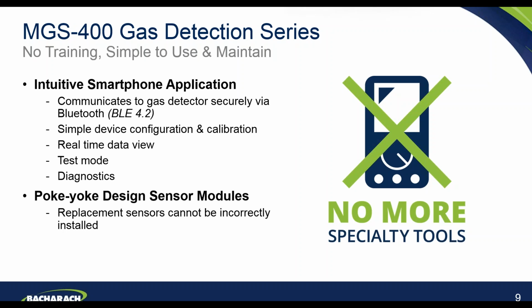In terms of the sensor modules themselves, they've been designed as a poka-yoke design, which essentially means that there is no way those sensor modules can actually be incorrectly installed. You can't put them in upside down or put them in the wrong way round. There is only one way that they can go in. So again, it makes that relatively foolproof and simple to carry out.